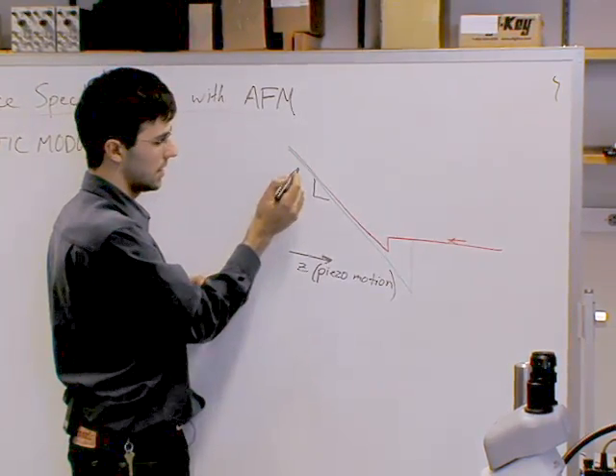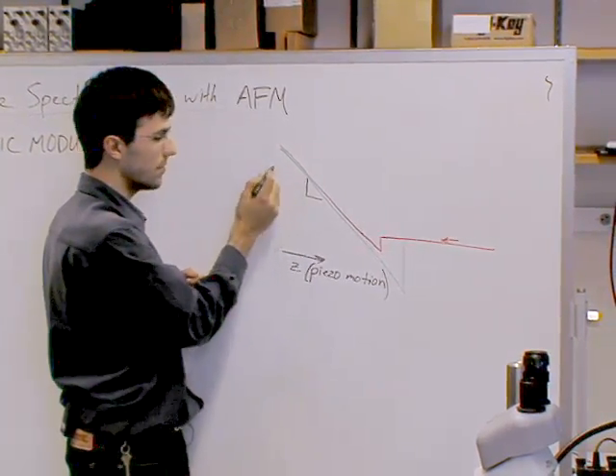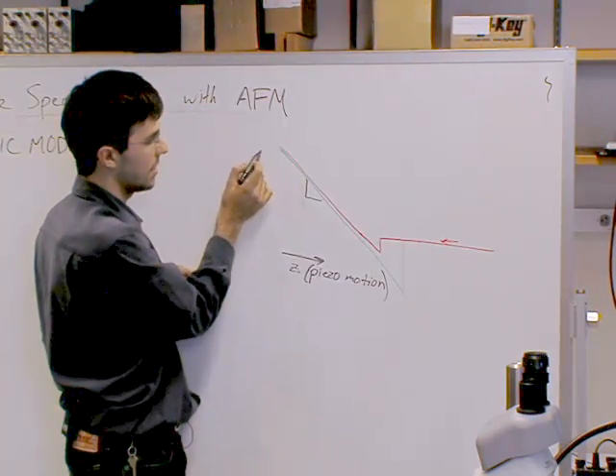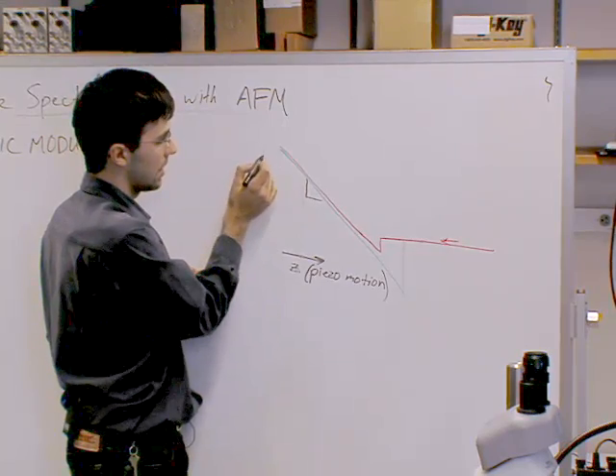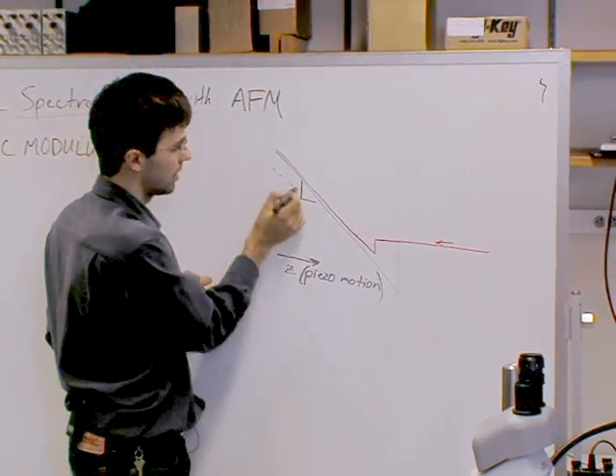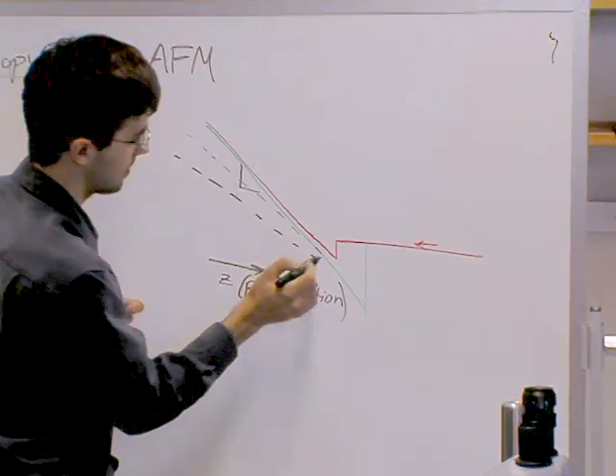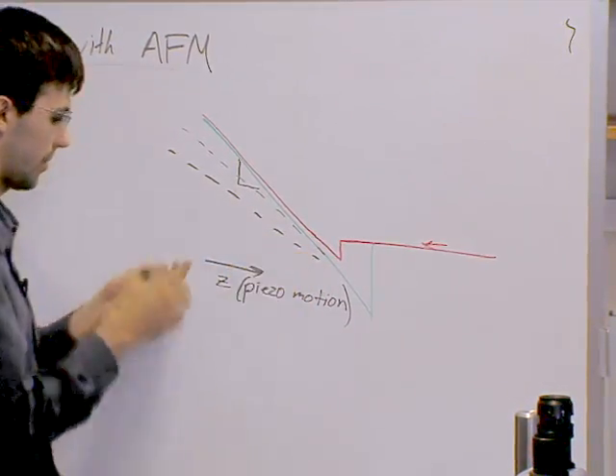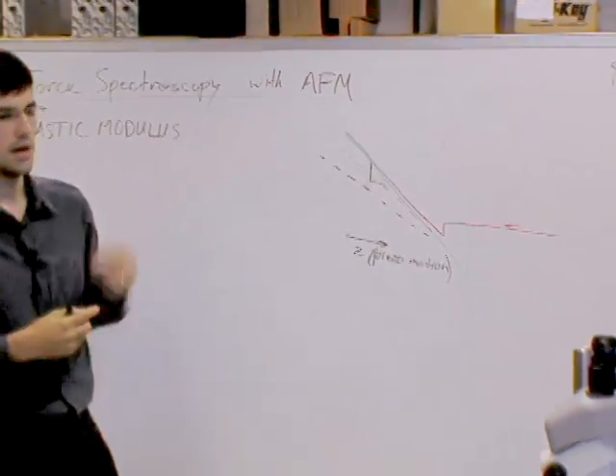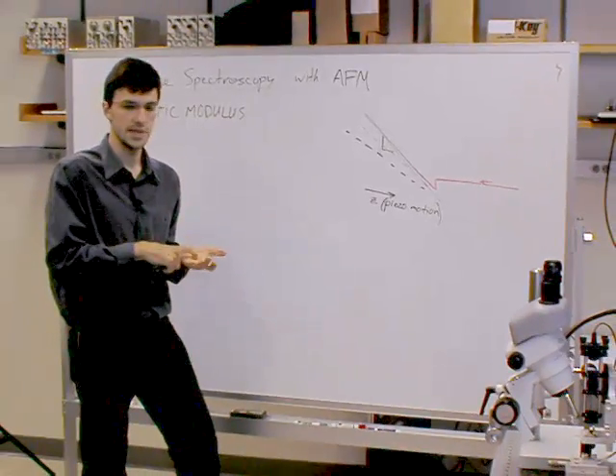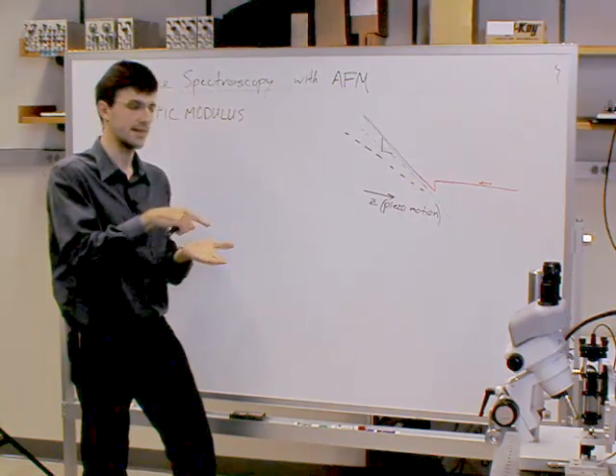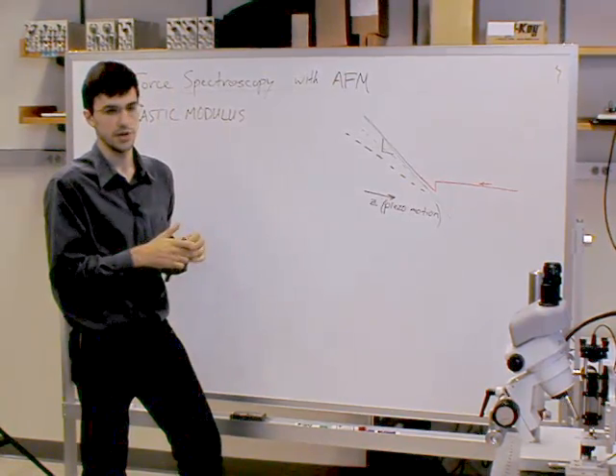So you have to relate the piezo motion to whatever the voltage is being applied to the piezo or somehow being read into the AFM. So the relationship between piezo motion to displacement of the spot on the photodiode then gives you a conversion factor for basically nanometers per volt of displacement. And that slope for different materials, you'll see a different slope. Typically, if you have a softer material, the slope will get smaller.